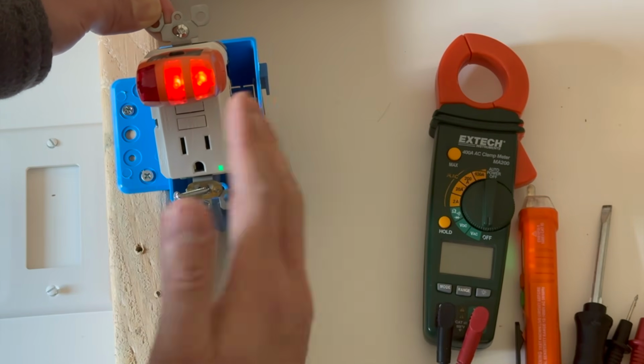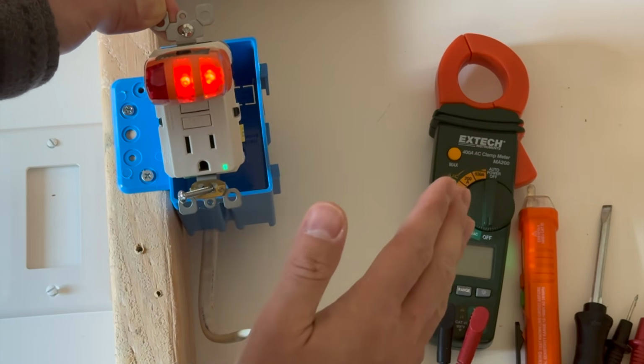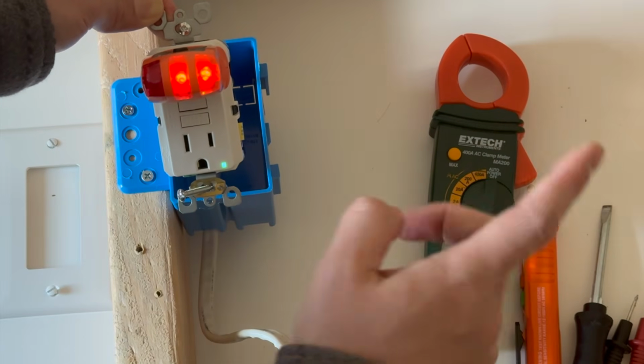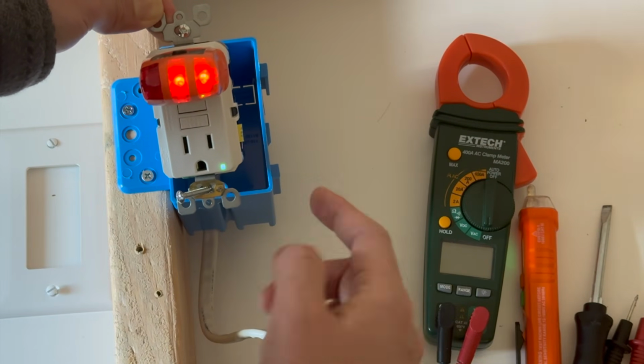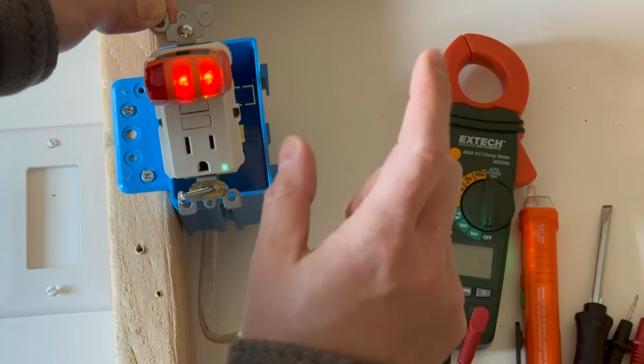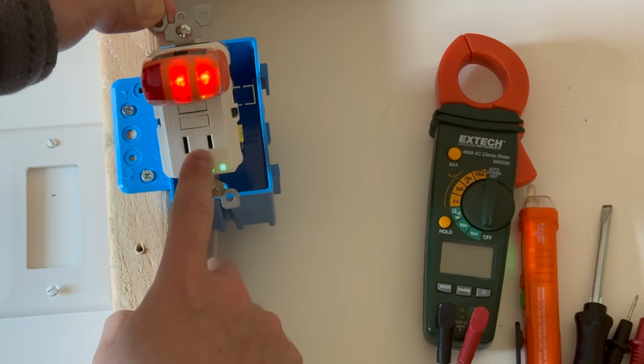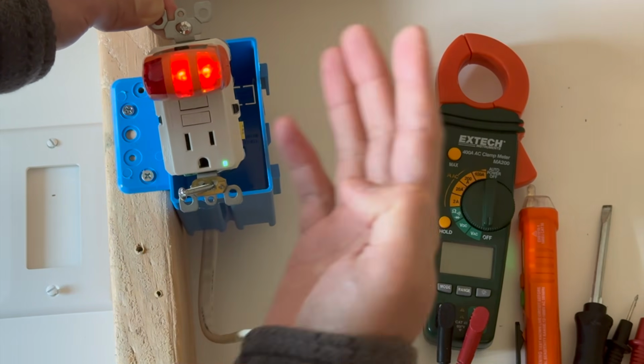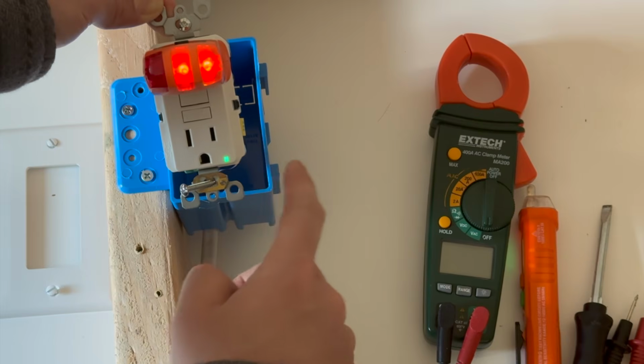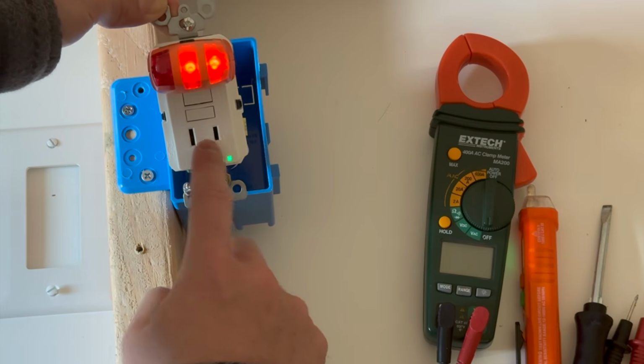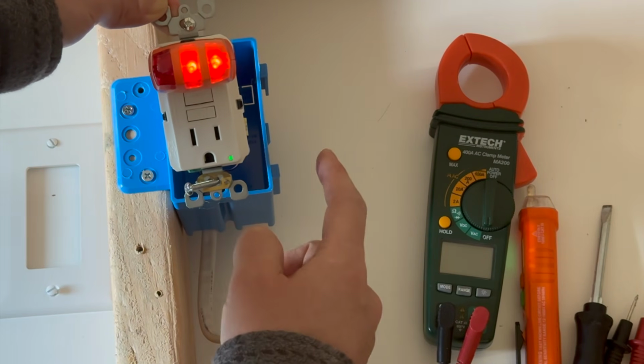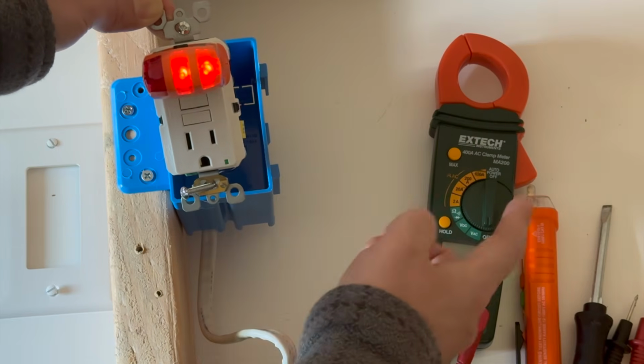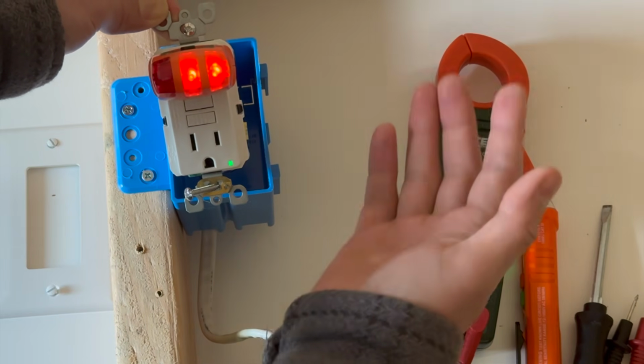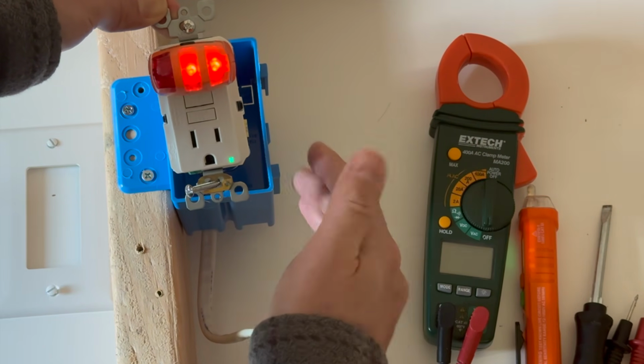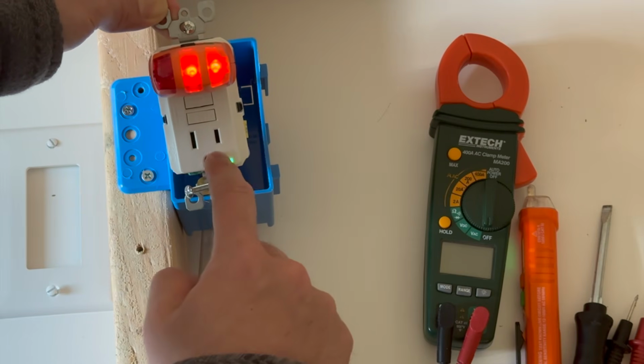If you're certain that that circuit is not switched, then you need to go take a look at the breaker and see if the circuit breaker itself is sending power to the circuit, or junction box. Sometimes wires to the GFI don't come straight from the electrical panel. It just jumps from the junction box. Maybe you have a loose connection in a junction box where the power is coming to this outlet.